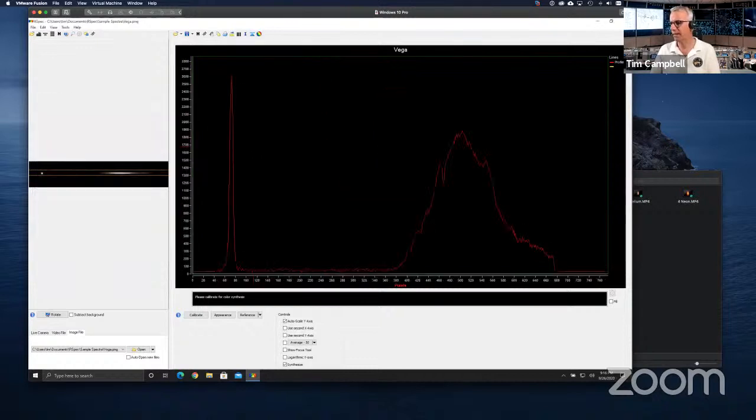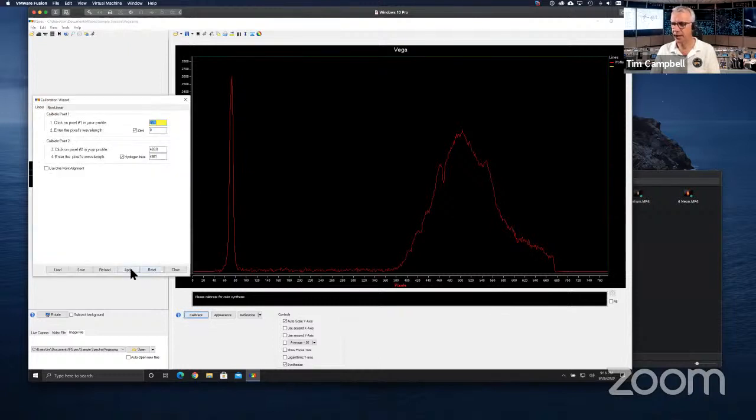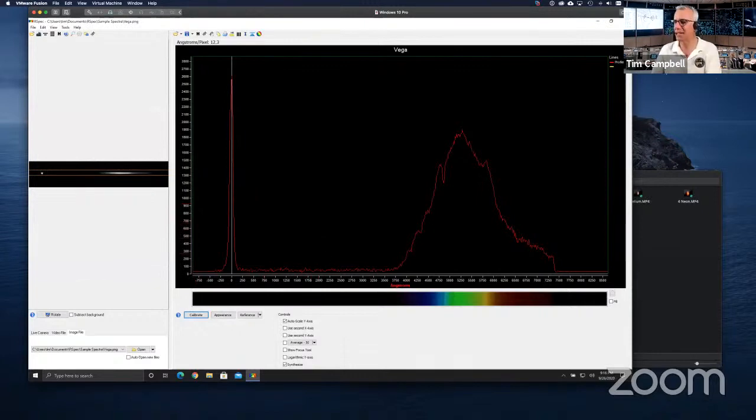Okay, now having done that, oops. It would help if I hit the apply button. There we go. Now, having done that, I have calibrated my spectroscope. Now, what it's showing me at the bottom here, now you actually see colors. Now, remember, this was not a color camera. This was a monochrome camera. But the computer's saying, yeah, but if it were a color camera, it would correspond to these colors precisely. So it turns out I can use a monochrome camera to detect the spectra.